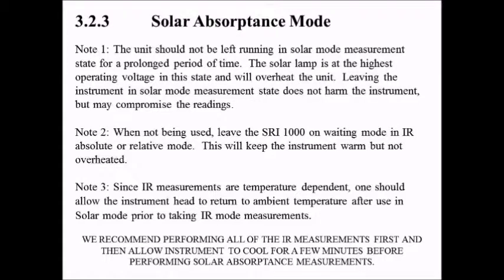Note 3. Since IR measurements are temperature dependent, one should allow the instrument head to return to ambient temperature after use in solar mode prior to taking IR mode measurements. We recommend performing all of the IR measurements first and then allowing the instrument to cool for a few minutes before performing solar absorptance measurements.